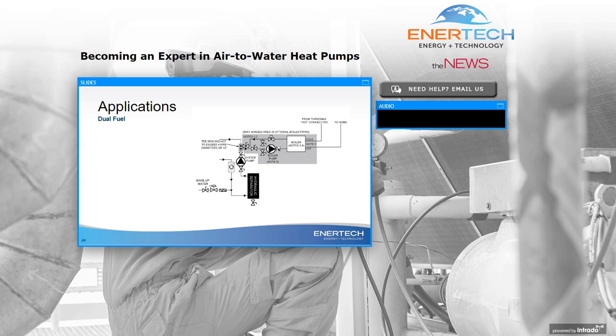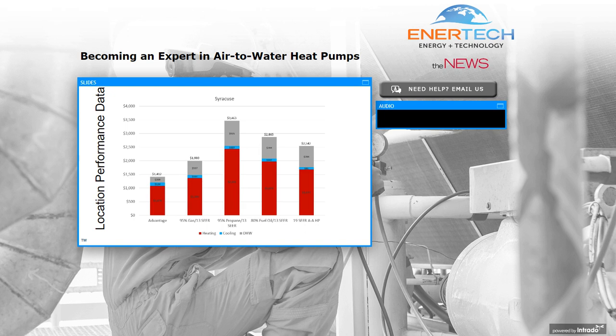If we go dual fuel, by piping that boiler in, and it may be a combi boiler like the one in the picture here where we're also providing some hot water, that can be controlled by the indoor module. So it will send a signal to the boiler whenever the boiler needs to come on. And at that, I will turn it back over to Tim for discussion on operating costs.